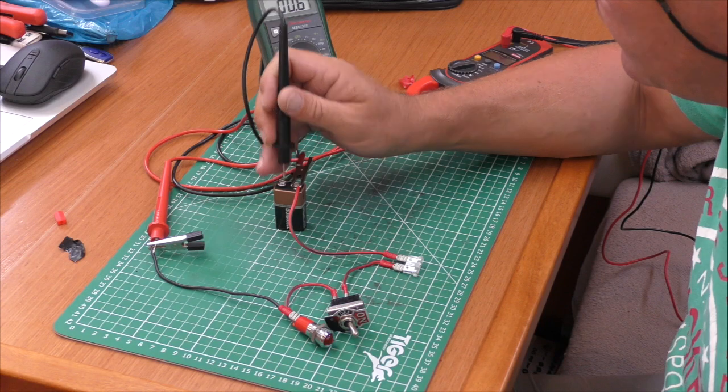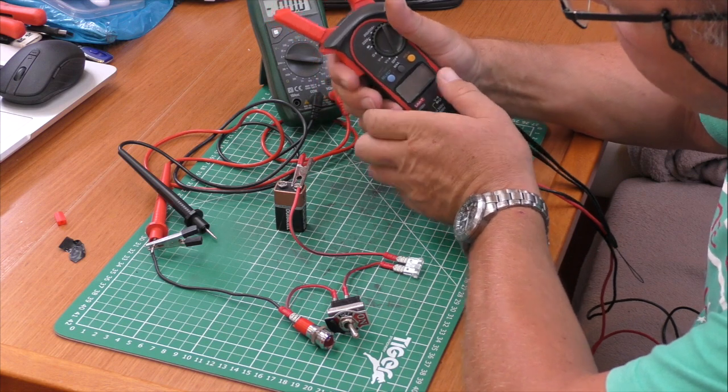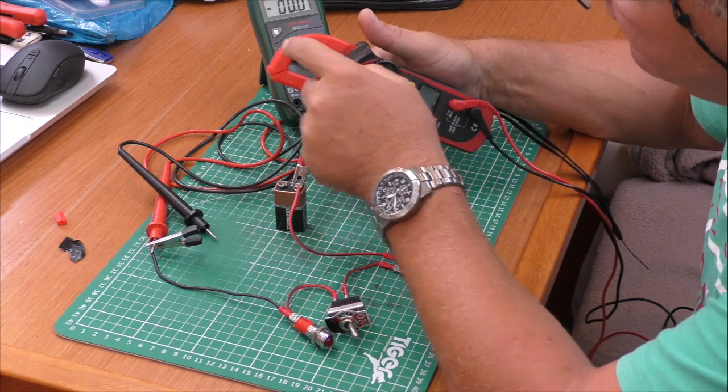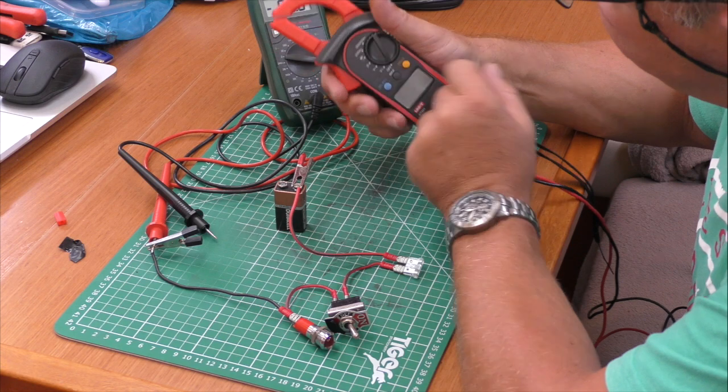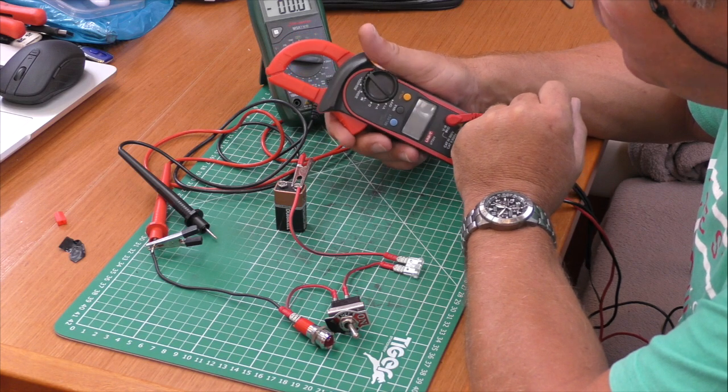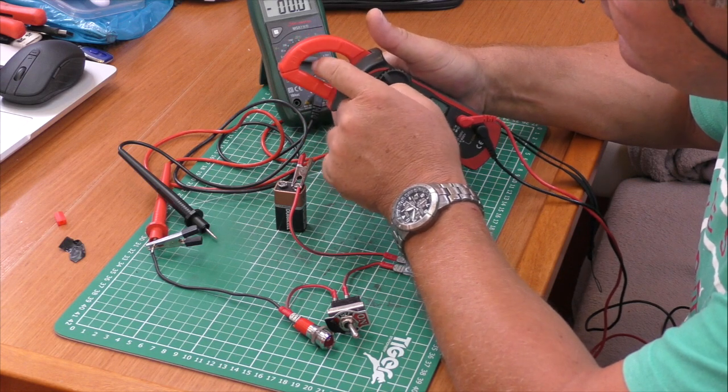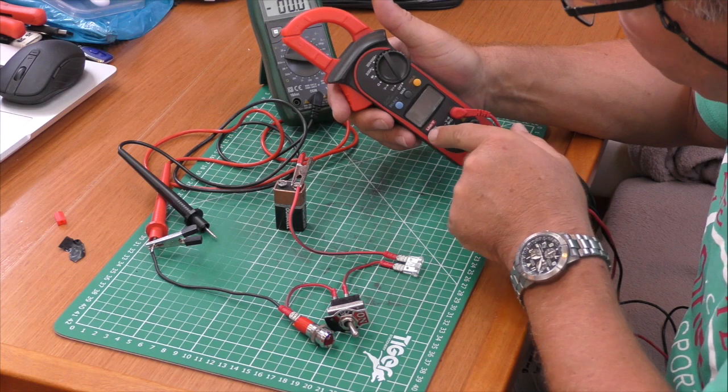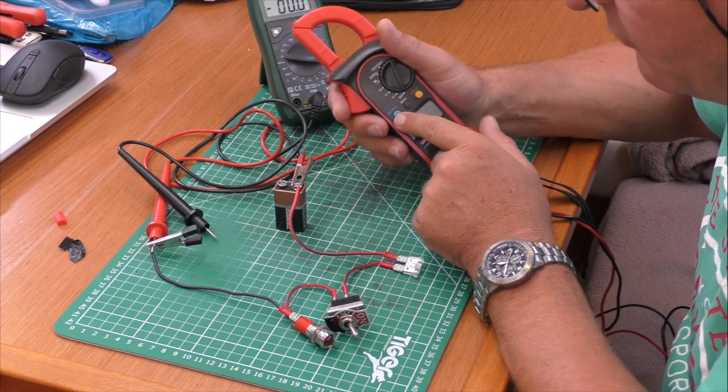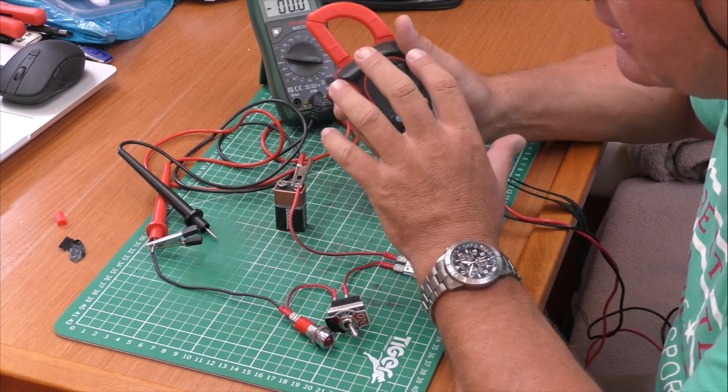Now the exception to this is when you use one of these clamp meters. With a clamp meter it works by induction. Remember we talked about how cables have magnetism running in them when they're live. This is an AC clamp meter but you can buy DC clamp meters and they work in the same way. They're not part of the circuit. The electromagnetic induction induces a current in a coil and that current is measured on the scale here. I believe that's a much safer way of measuring current rather than putting your meters into a circuit.